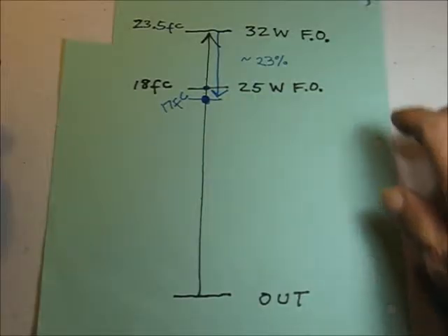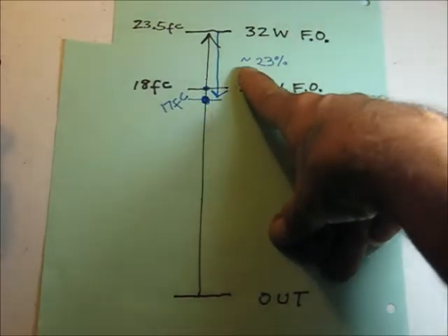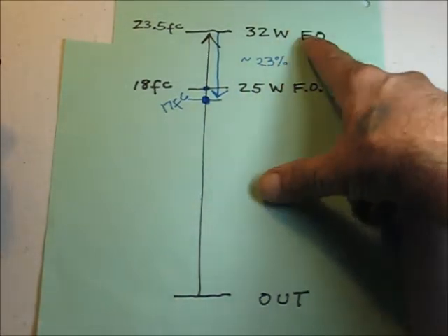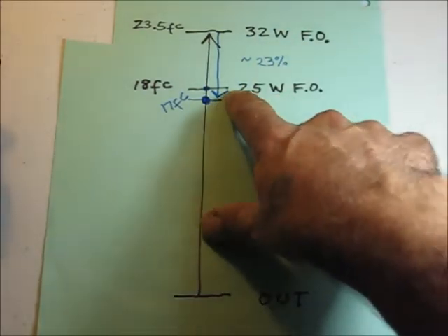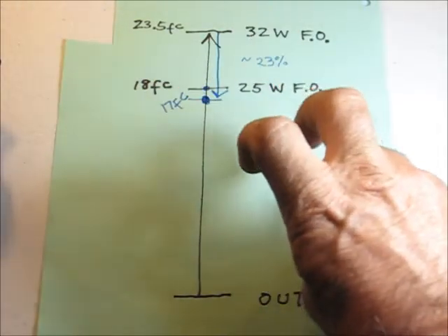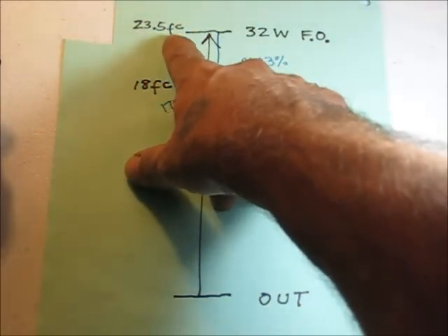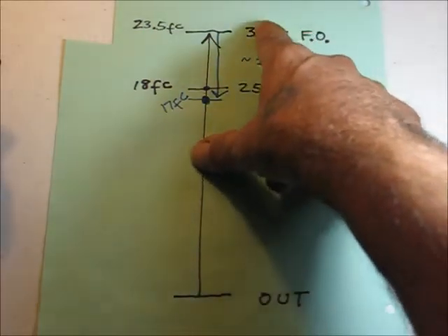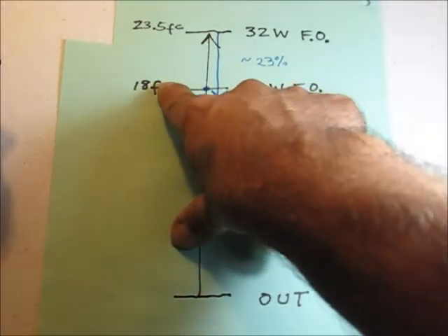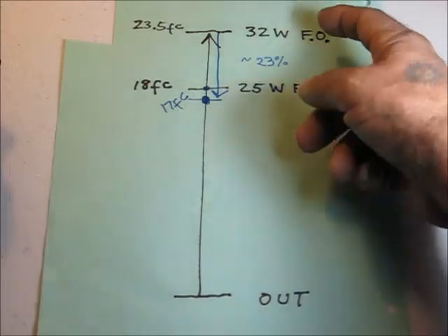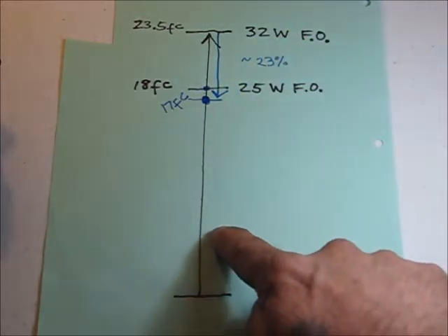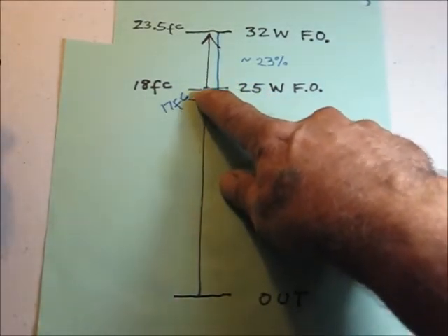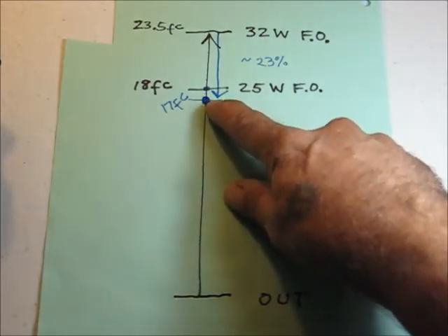We had 32 watt lamps and 25 watt lamps. And these are to simulate aging and yellowing. These are 5000K. These are 4100K. These were capable of producing approximately 18 foot candles at our reference location. And the 32-watters were capable of doing 23.5. So we needed to tune these down to below the maximum output of the 25-watters. And then when we reinstall the 25 watt lamps, we want the controller to bring them back up to our setting for the 32 watt lamps.